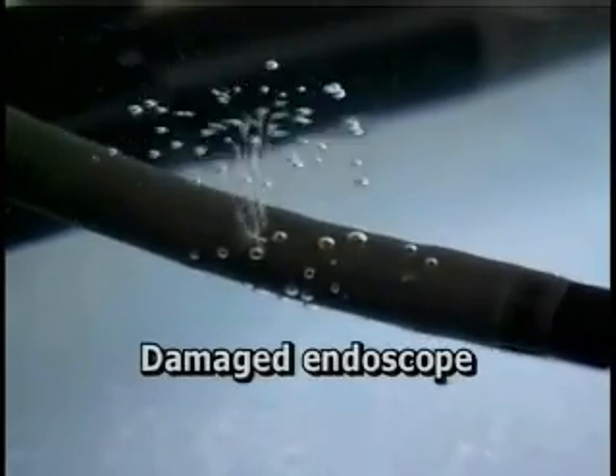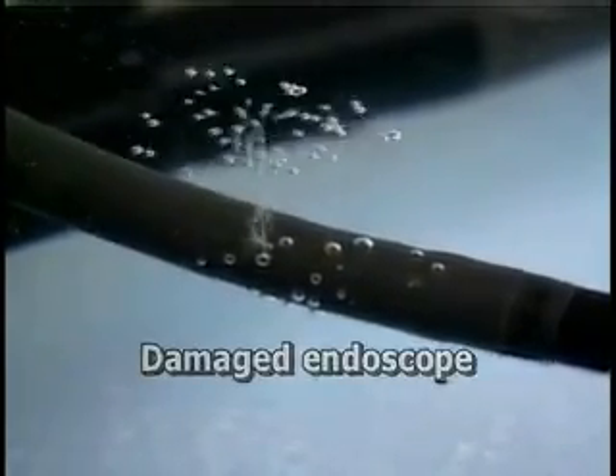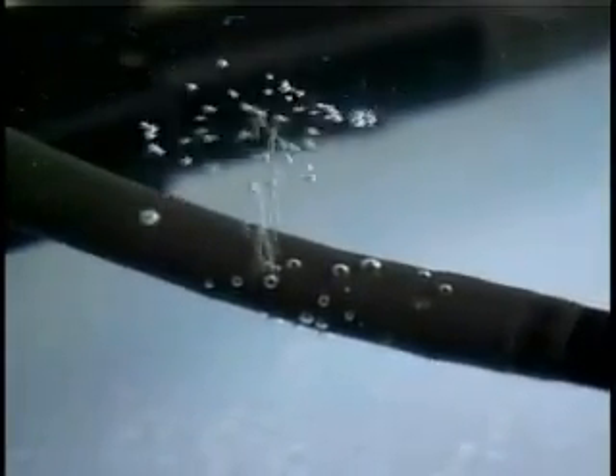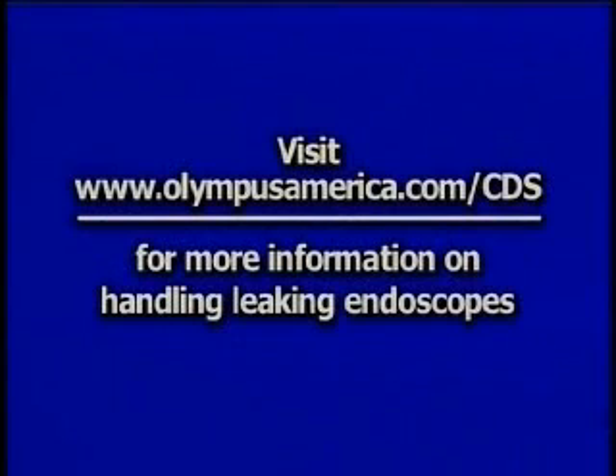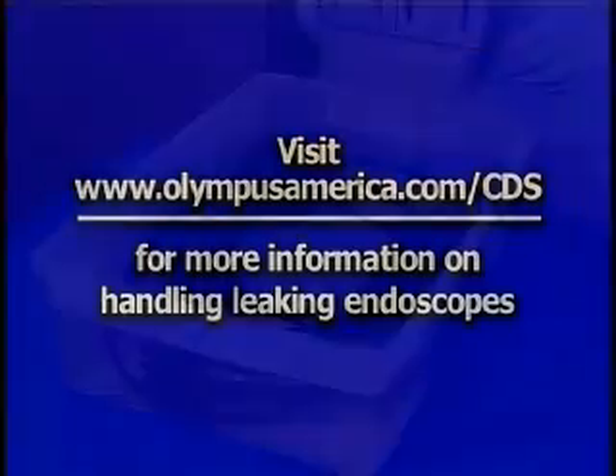Leaks like this will allow fluids to penetrate and damage the endoscope. If you observe such a leak, do not turn the air supply off. Rather, remove the endoscope from the water. Blow out the channels with air and dry the endoscope prior to turning off the leakage tester. Contact Olympus for instructions on how to reprocess a leaking endoscope prior to sending the endoscope to Olympus for repair.